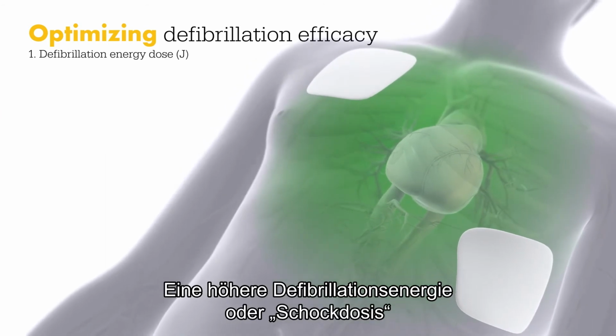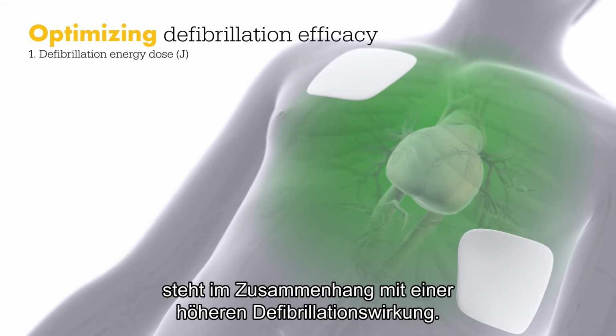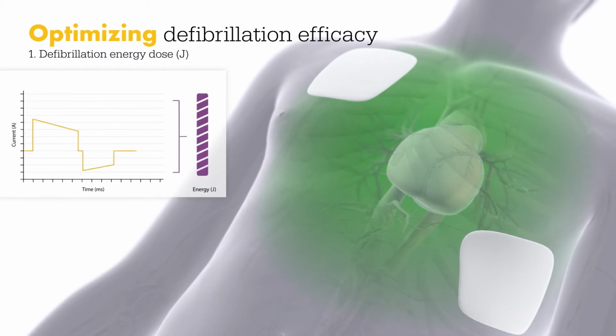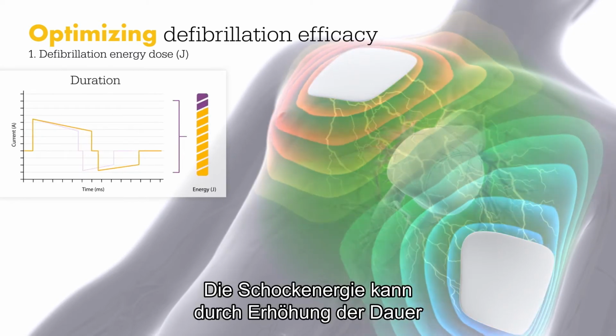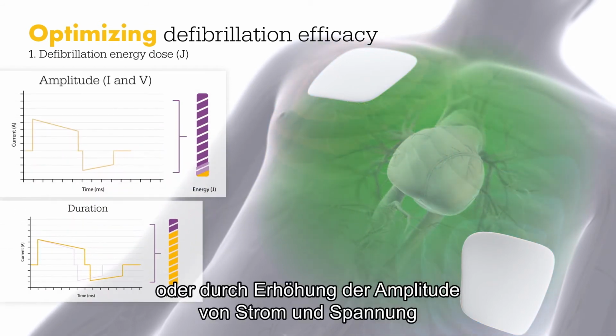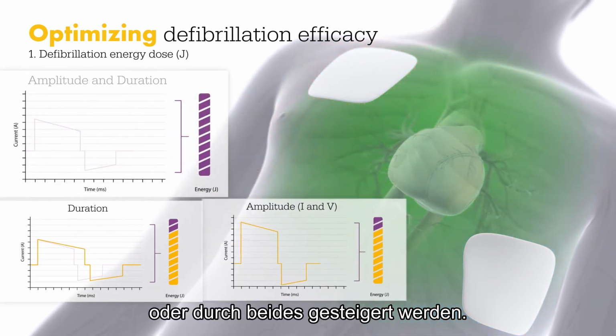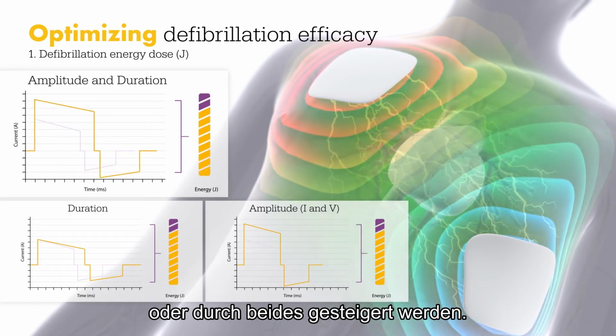Higher defibrillation energy, or shock dose, is associated with higher defibrillation efficacy. Shock energy can be increased by lengthening the duration, or increasing the amplitude of current and voltage, or increasing both duration and amplitude.